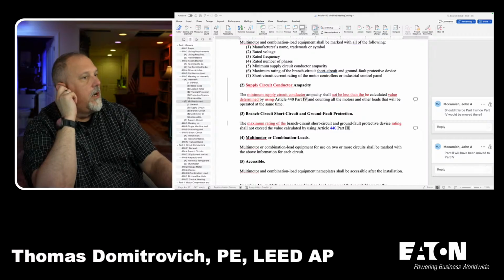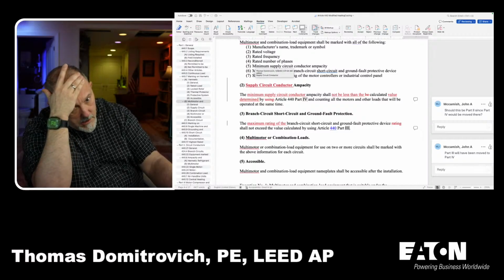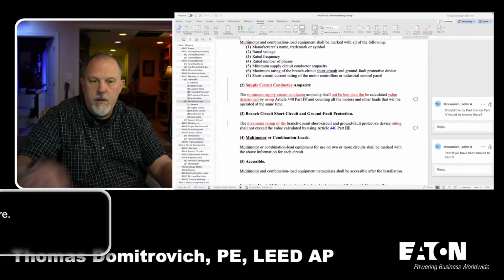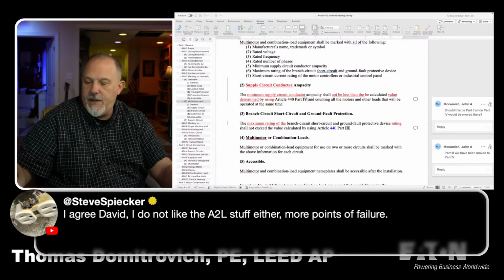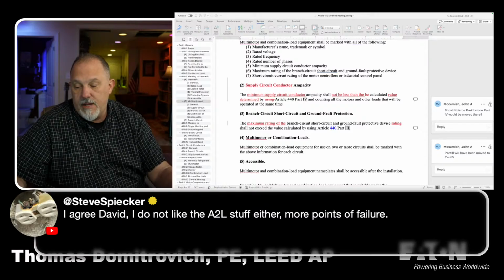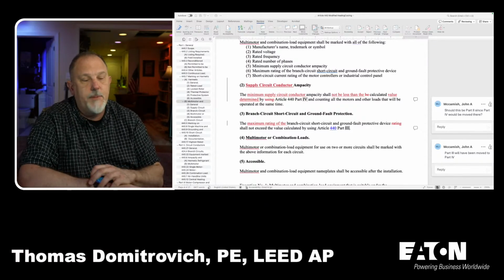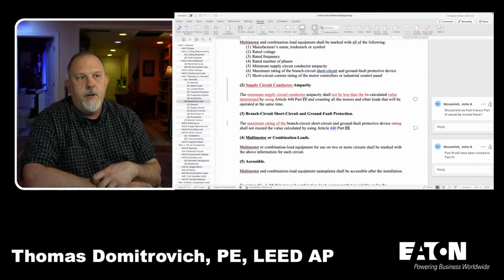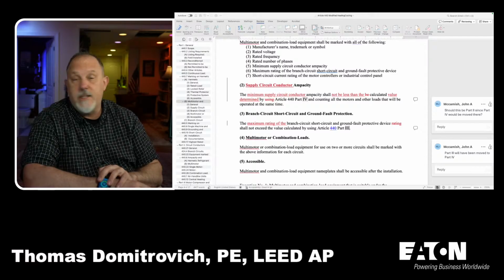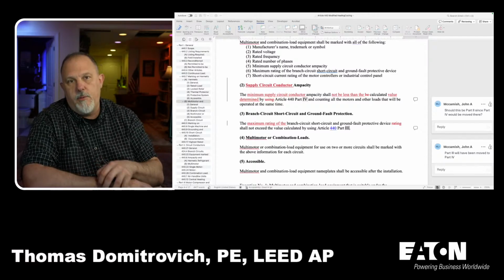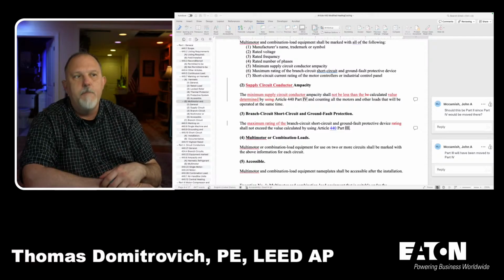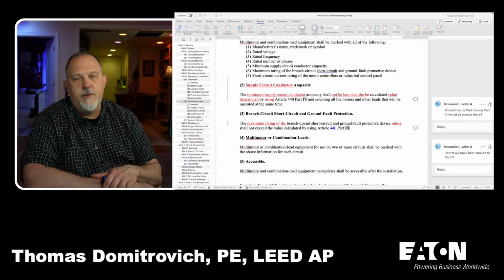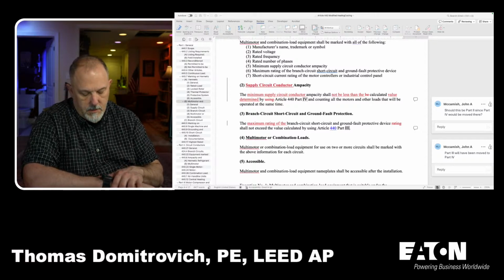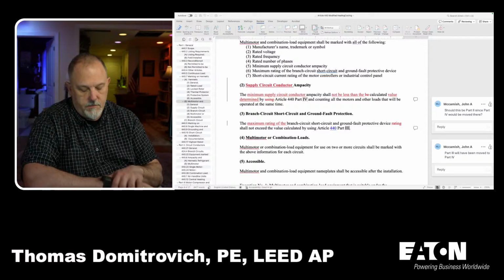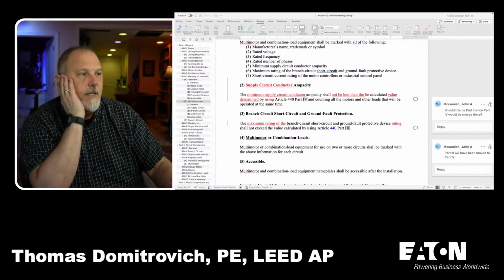Supply circuit ampacity. Oh, so I changed this. Steve, I agree, David. I do not like the A2L stuff either. More points of failure. Yes, and here's what I was told: when those fail, and if there's no power to deal with it, you get the kaboom, and that's not good. I don't know that I agree with the kaboom part, but they said it's highly flammable, and they're using that to justify removing GFCIs. So anyway.